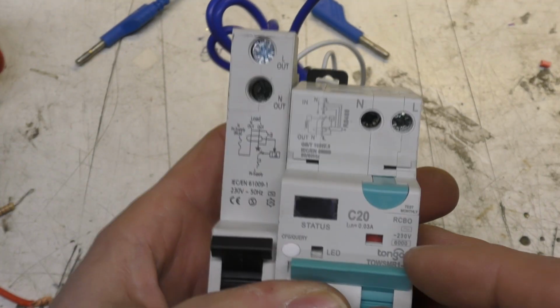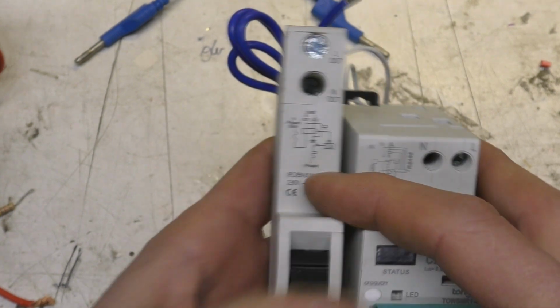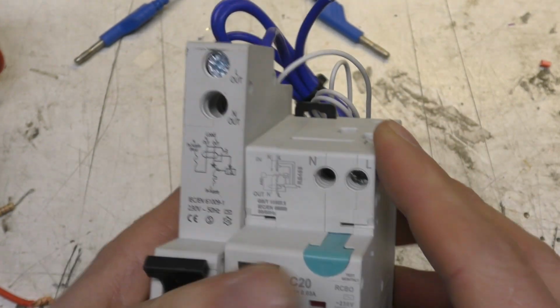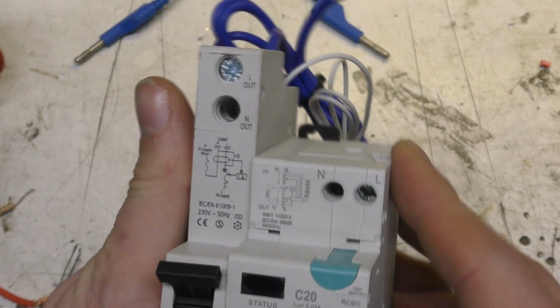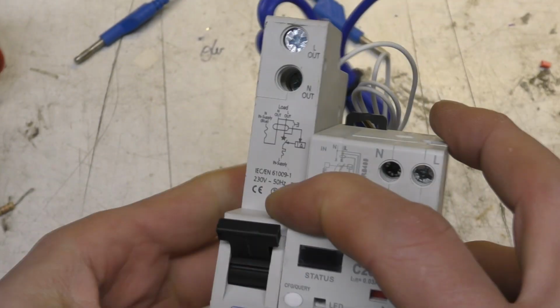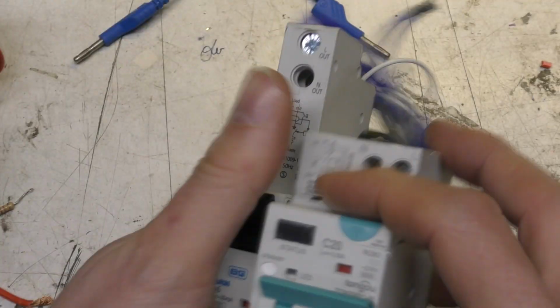These are both advertised as being RCBOs, which stands for residual current breaker with overcurrent. So they combine the function of a residual current breaker. Again, we call them RCDs in the UK. Elsewhere, they're sometimes called earth leakage or GFCI, ground fault current interrupters. They all basically do the same thing. So the idea is that they protect the downstream circuits against overcurrent, but also leakage from mains to earth.